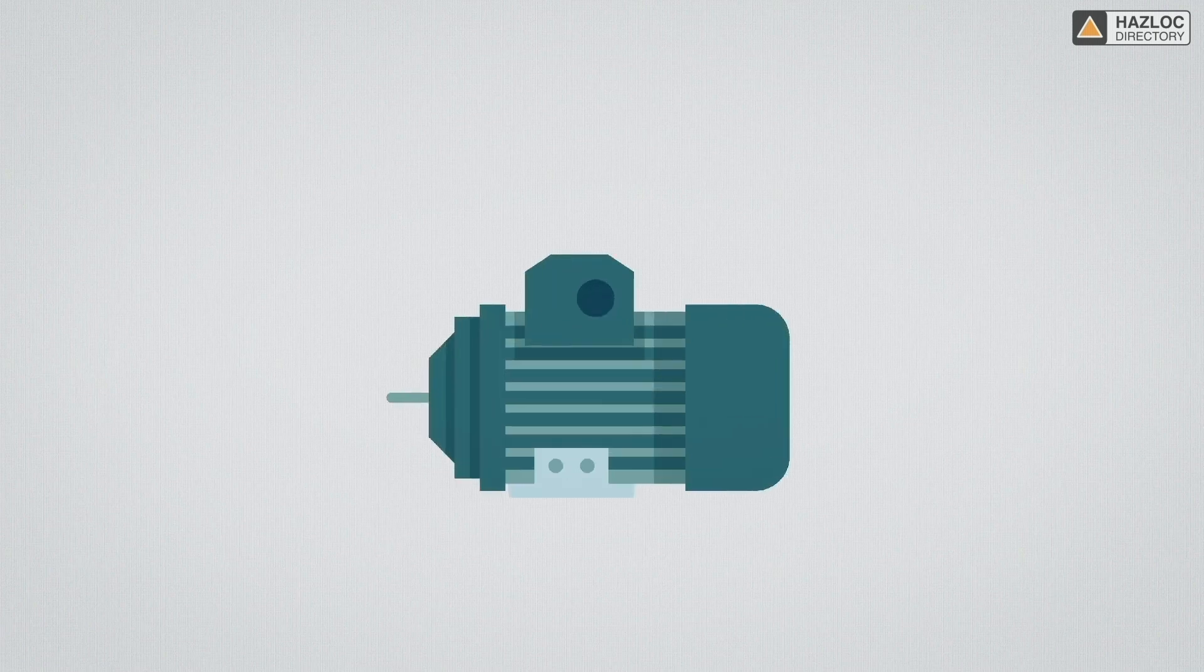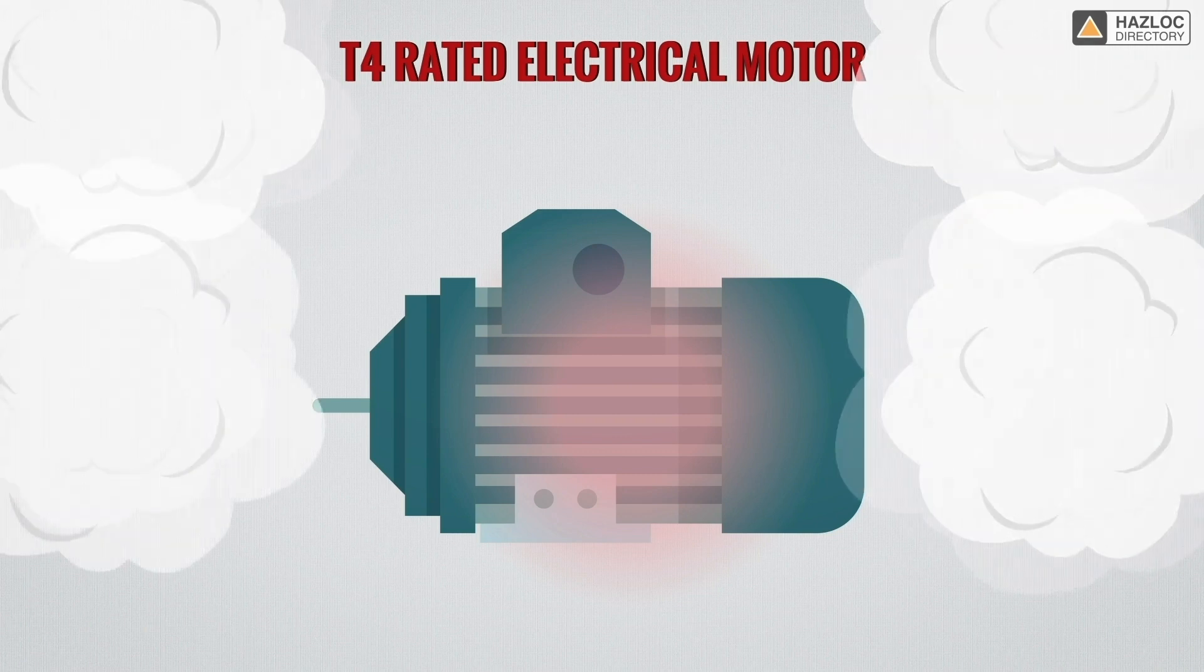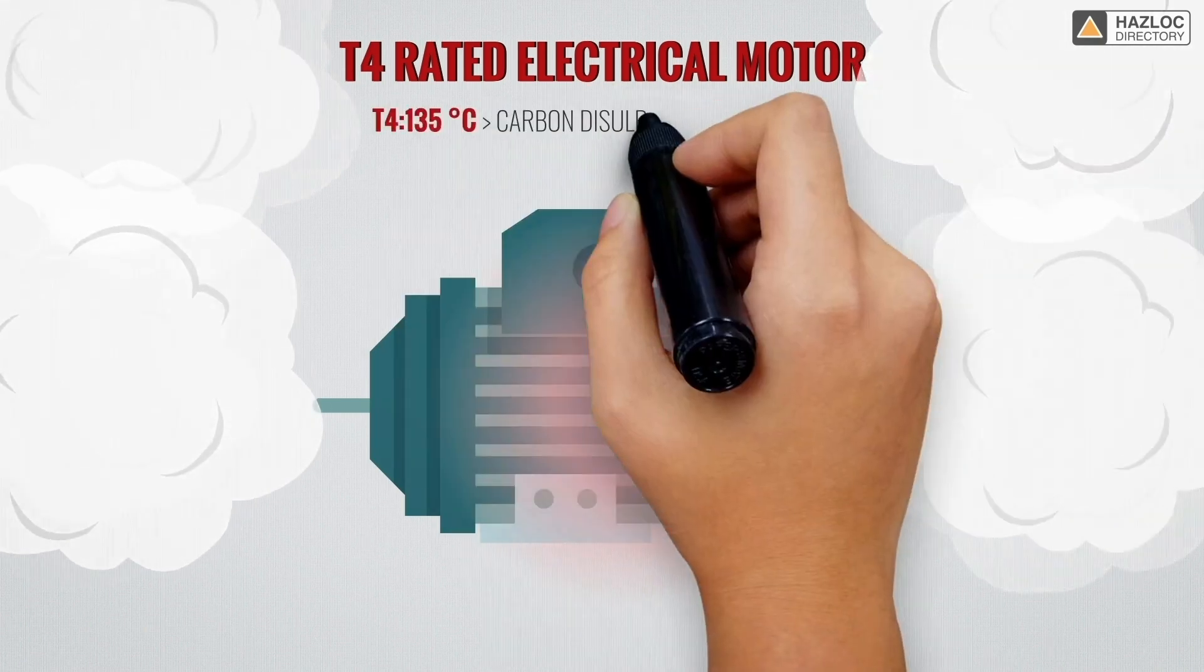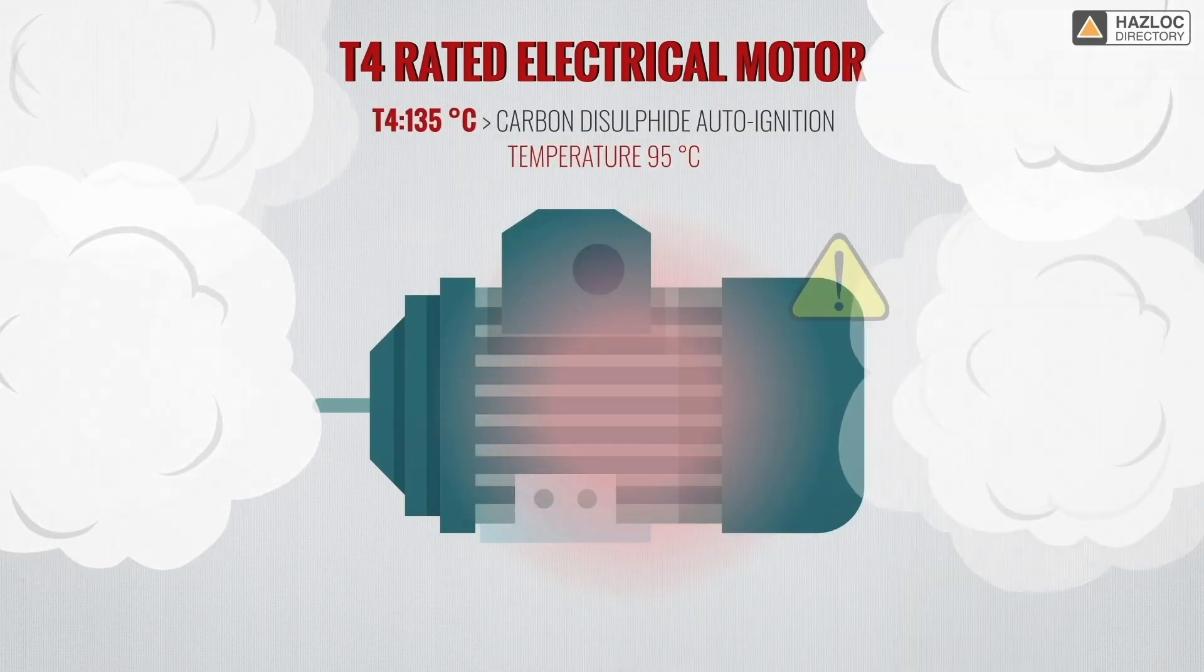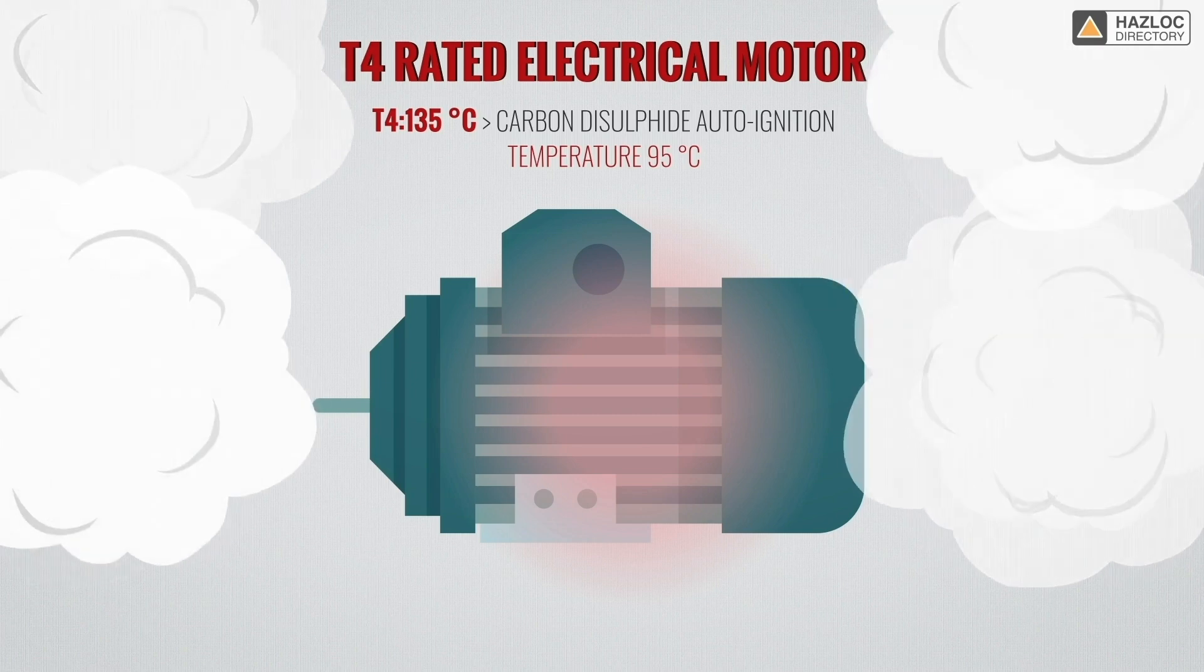Let's use an example to clarify these concepts. We have an electrical motor rated as T4 for installation in a hazardous location. If this motor were installed in a location in which carbon disulfide with an auto-ignition temperature of 95 degrees is present, the result would be an explosion.